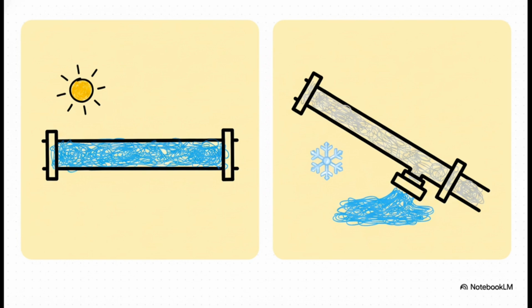Instead of water, it holds pressurized air or nitrogen in the pipes. All these pipes are pitched or sloped to help drain out any moisture. So when a fire activates a sprinkler, the pressurized air escapes first. That pressure drop trips a dry pipe valve, which then finally allows the water to flood into the piping network and out the head.